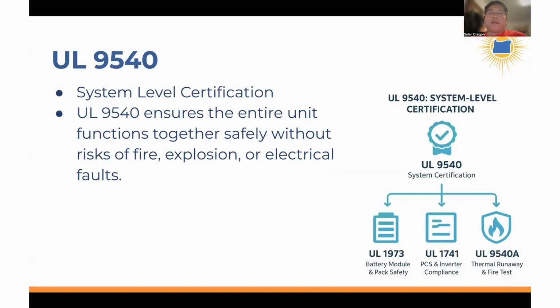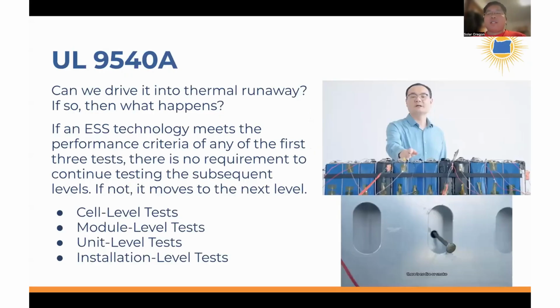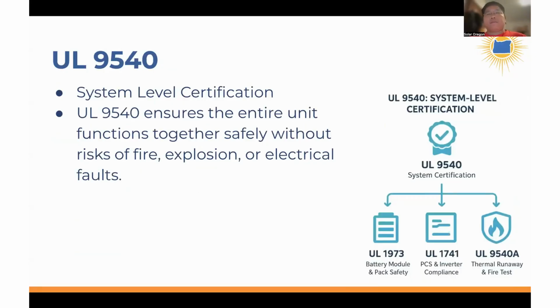If the batteries have been tested to be safe from overcharging, from damage, even if you puncture with a nail and it's still safe, then it doesn't really matter whether it's charged by one inverter versus another. It's still safe because the battery management system is properly managing the battery internally. It depends on whether your AHJ requires a UL 9540 certification. If it doesn't, you might have a lot more freedom to choose an inverter and battery that isn't matched and independently certified.